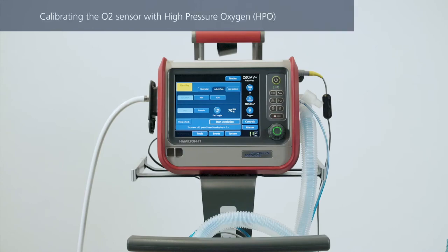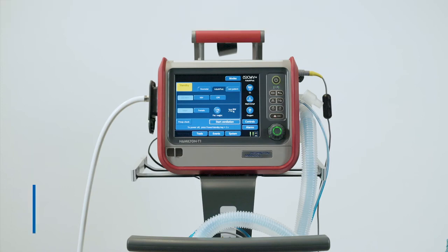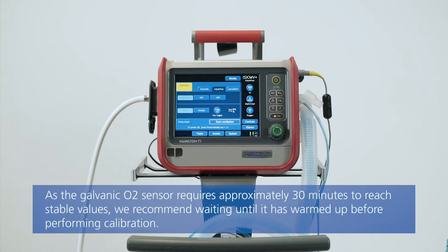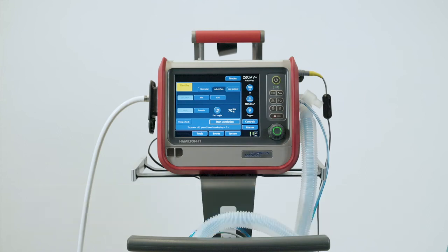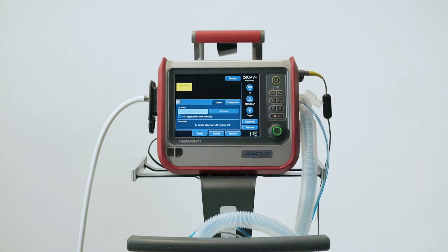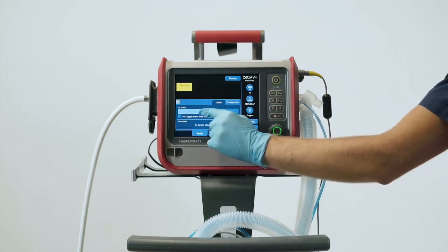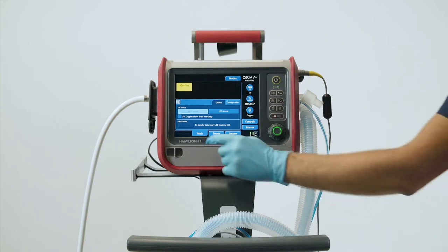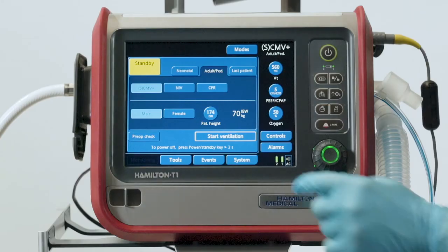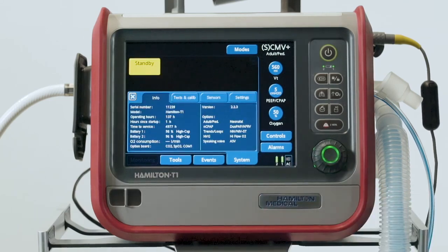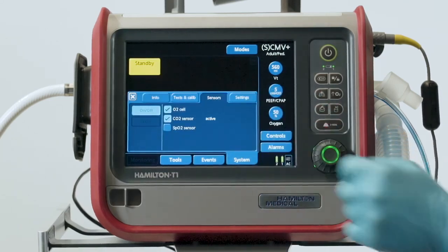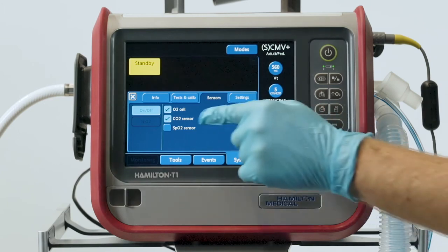You only need to calibrate the oxygen sensor after a new galvanic oxygen sensor has been installed, or if there is a related alarm. You can calibrate the sensor either when the ventilator's in standby or during active ventilation. Calibration takes around 2 minutes. Firstly, select the appropriate oxygen source. And make sure the oxygen monitoring is enabled.